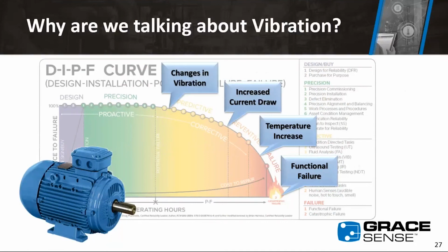But what we're focused on is the vibration side. This happens well in advance of any of the other symptoms that we see here, the current draw or the temperature increase. Vibration will detect if a bearing is starting to get some damage in the raceway, just little spalling, or if a ball has a dent in it and things like that. The vibration analysis can pick up on that. That's why we're really encouraging this, because it gives you the most warning that's really possible to address the issue.